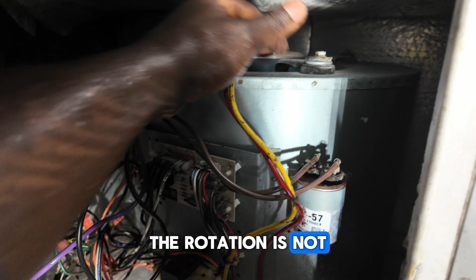Now, to test this motor, I can definitely unplug this one. So I'm bypassing this switch, right? Take out this one, and I'll also unplug this one. Then I will look for a way to power it directly here. Take my 240 volt to one of these terminals, maybe one here and this purple on the other side. If I do that and this motor is working, then it should run normally. Okay, so that is a way you can test it. For now, we are not going to do that because I already know that this motor is bad just by rotating it. Sending my finger here to rotate it, the rotation is not good. So that motor is bad. That is a way you can test that motor.